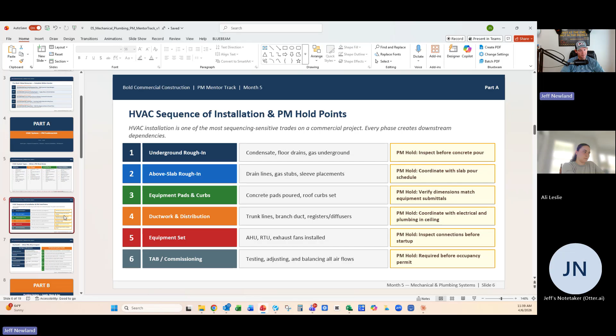It's typically a contractual requirement, but a lot of times the HVAC contractors will exclude it. The reason is, like having a testing lab separate from the general contractor, you want the test and balance done by an independent third party that doesn't necessarily work for the HVAC subcontractor, just for transparency. It's not that you think they're going to do something dirty, but at least there's never any question as far as the test and balance report.